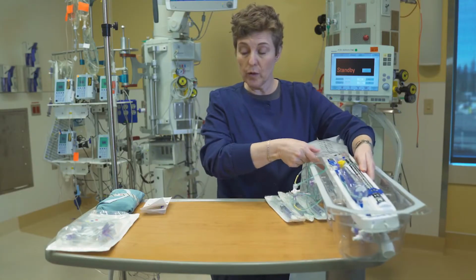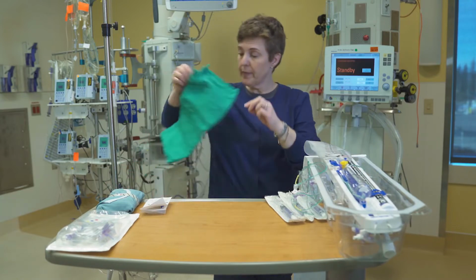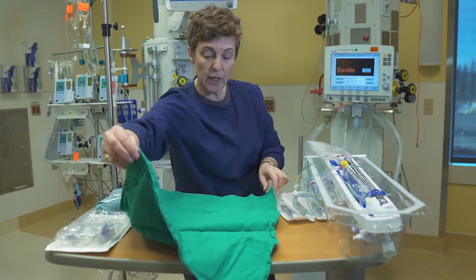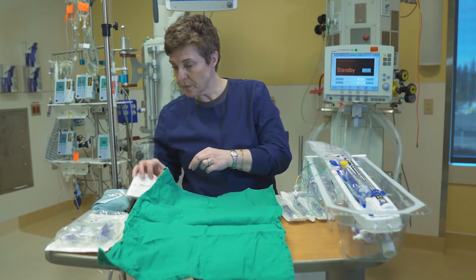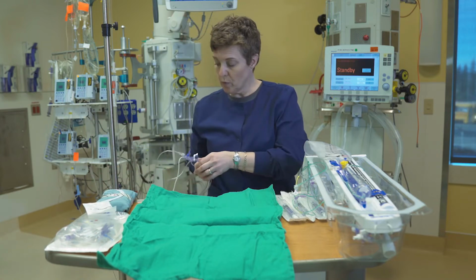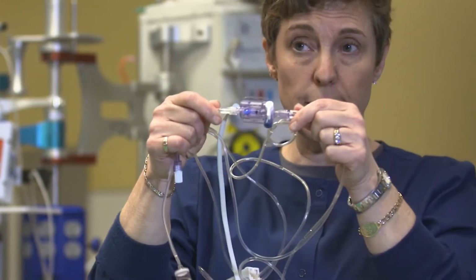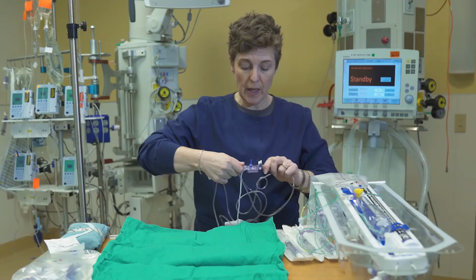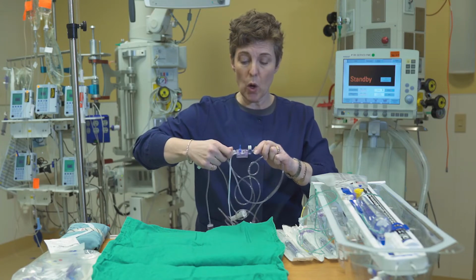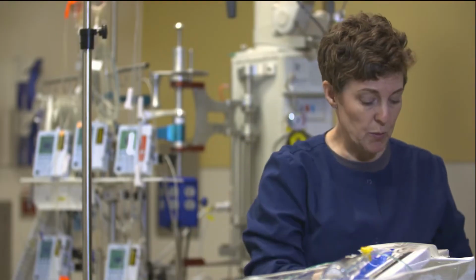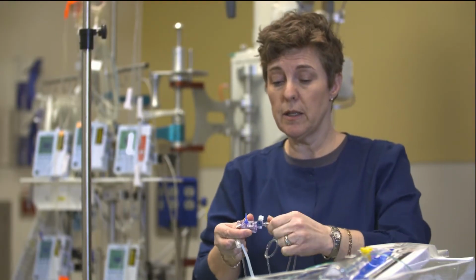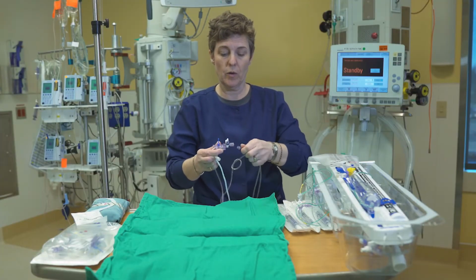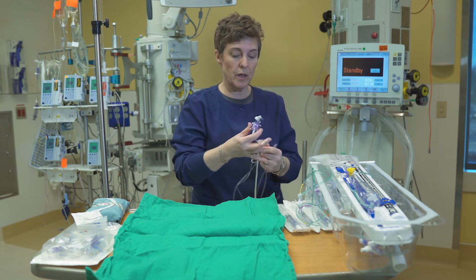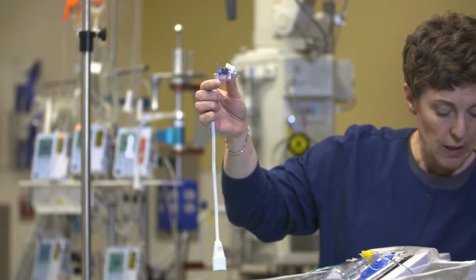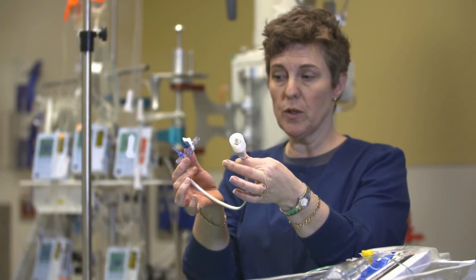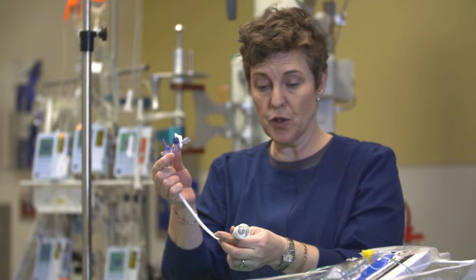I'm going to open up my huck towel first. And I just happen to have one here waiting. Just gives myself a clean area to be working within. And I'm going to have a piece of equipment ready. So this is my pressure line. So you're going to use a pressure line and you're going to remove both ends of it so that all that you're left with is the transducer. I'm going to dispose of that piece, and there we go. So all that is remaining that I'm going to be using is the transducer and the pressure cable that you will then plug your cable in to go to your monitor. So those are the two important pieces that you're using.